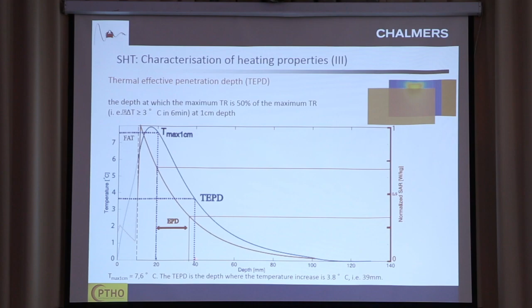What is important is that if we draw the aperture of the applicator, this thermal effective field size should ideally be larger, because then we can place 2 applicators just beside each other to cover large tumors. The second important parameter is the thermal effective penetration depth. That's defined in the vertical cut of the phantom. Again, we consider the maximum temperature at 1 centimeter depth, and then we consider 50% of that, which in this case is 3.8 degrees C. And then we look and measure the depth. So for this particular applicator, the thermal effective penetration depth is 39 millimeters. It means that with this device, tumors up to a depth of 4 centimeters can be treated.